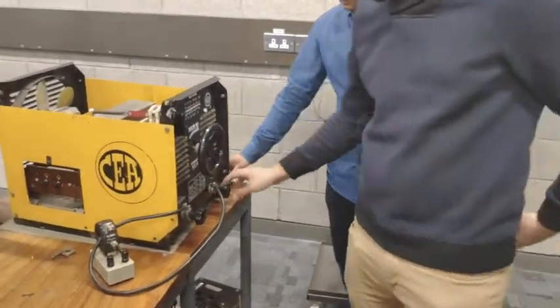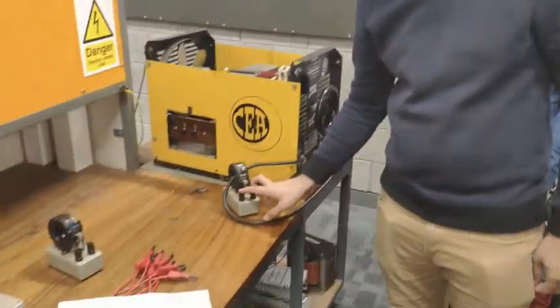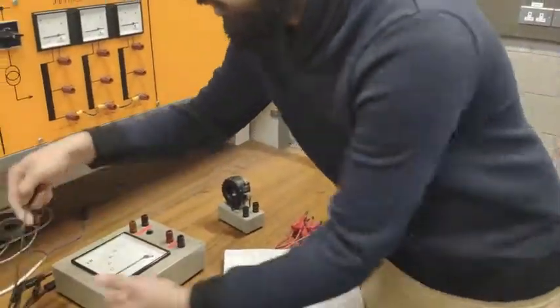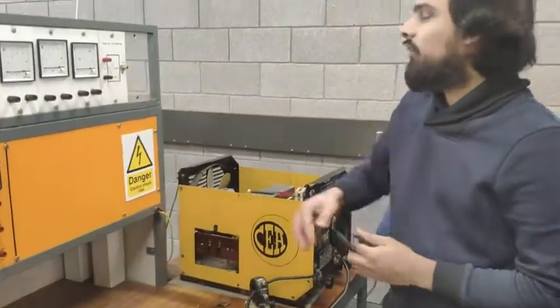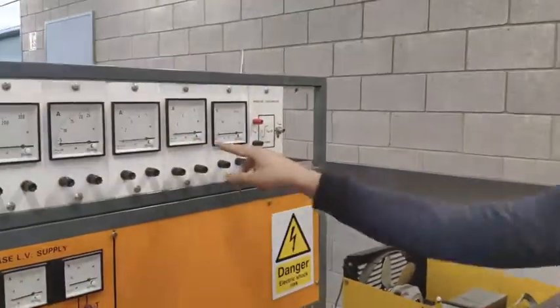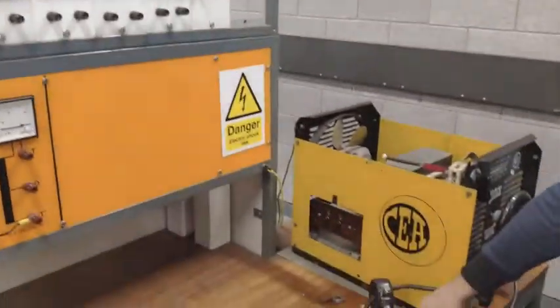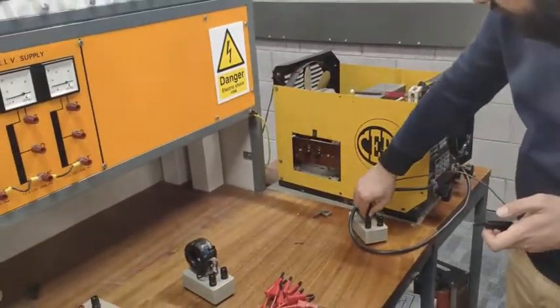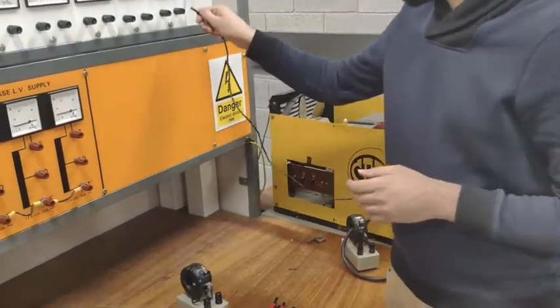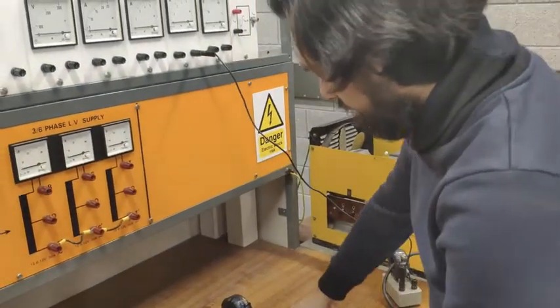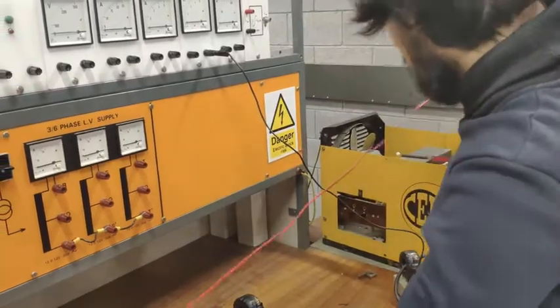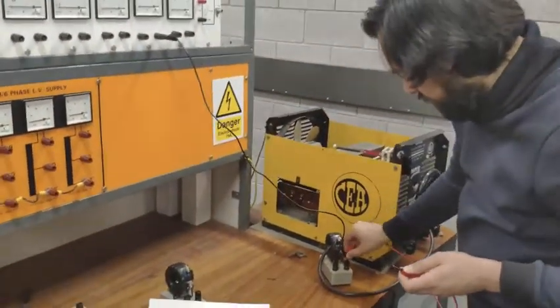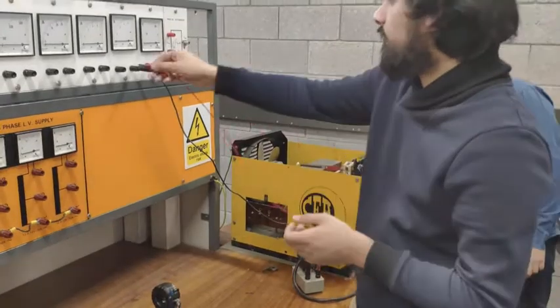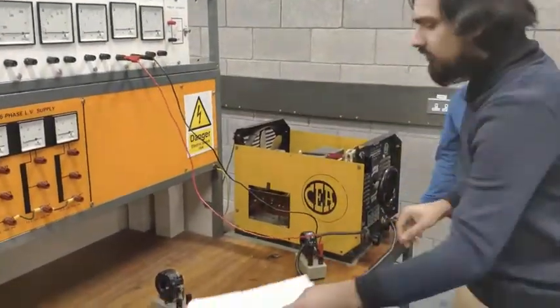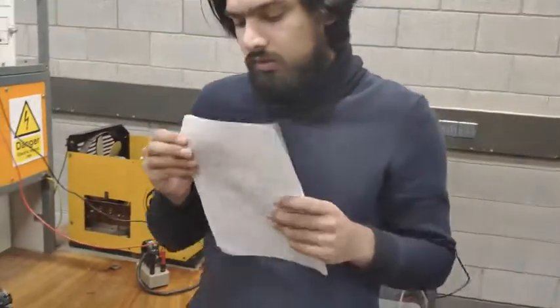So the secondary connection has been done. From here you can read amps. So I will make a connection to the ammeter, and I will use the 5 amps meter because the rating of this one is 5 amps on the secondary. So the secondary part is done.